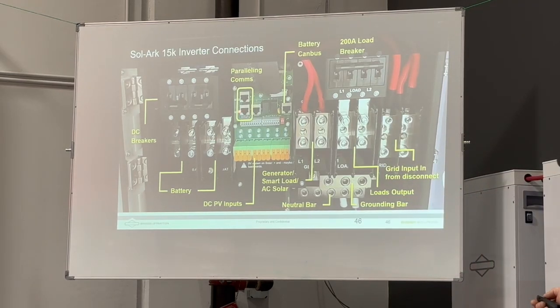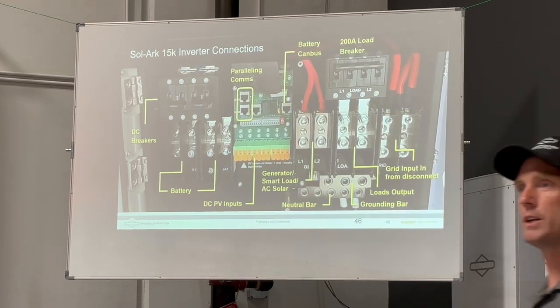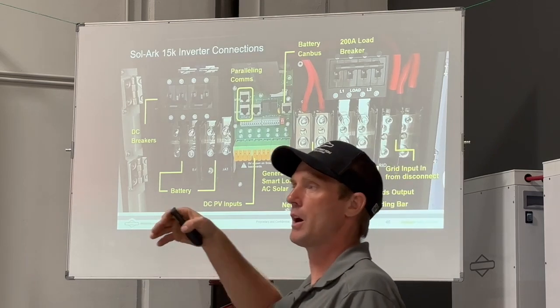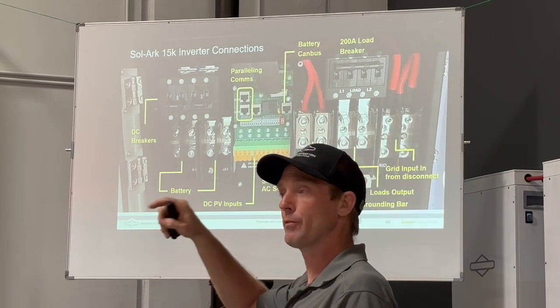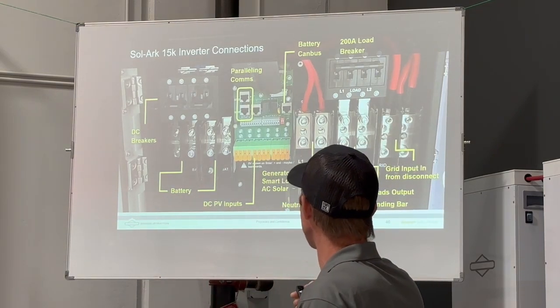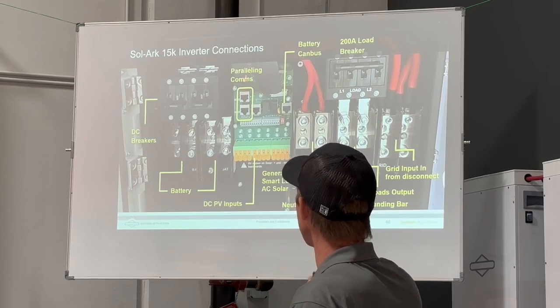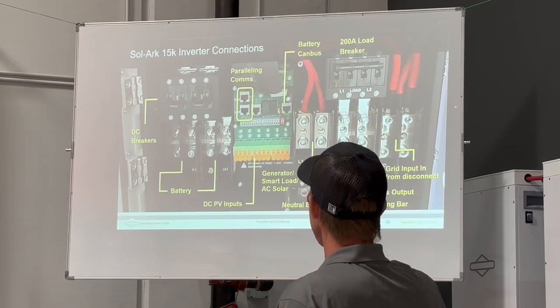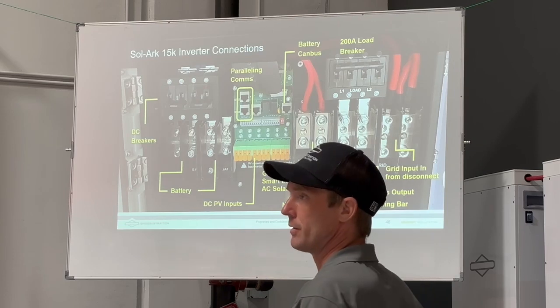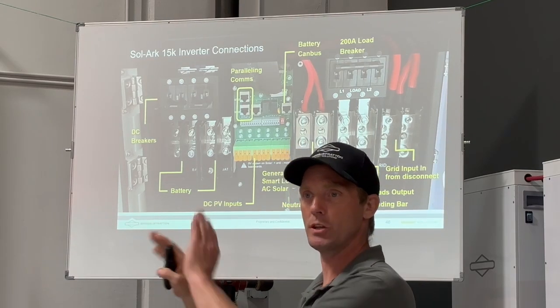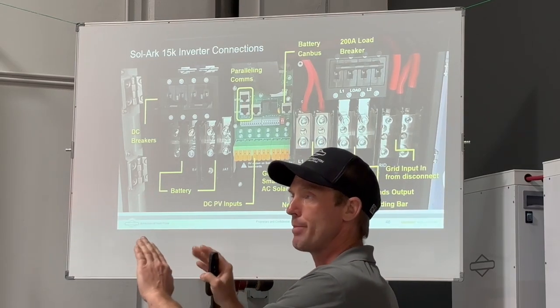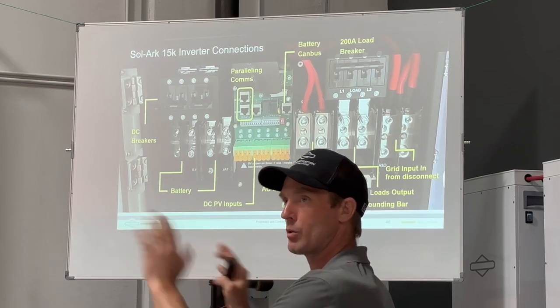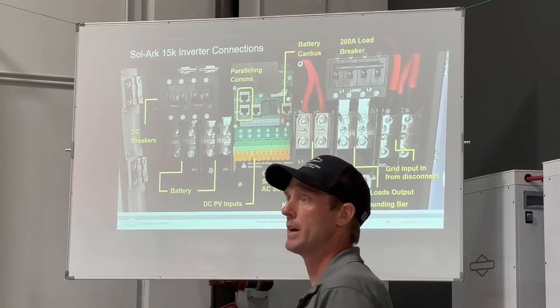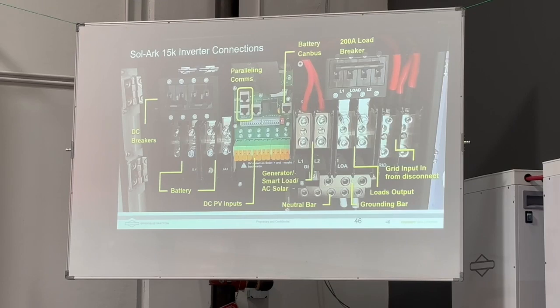Here is where the paralleling communications happen. So remember how I said if you wanted to parallel 3, 4, 5 Sol-Ark 15Ks, you would have closed loop. So inverter 1, let's suppose I had 2 of these. I'd go out of this one to the second inverter, and then out of the second inverter back into the first one. And now I have closed loop communications between the two inverters. So when they need to supply power, they communicate with each other how much power to supply, and so they're splitting the demand, the load. Sorry. Go ahead. So when you're running in parallel, right? Mhm.